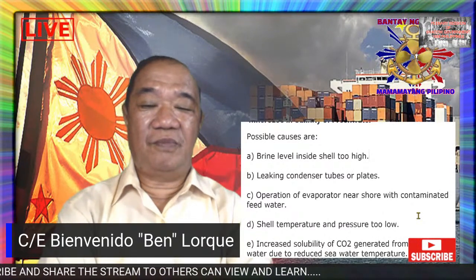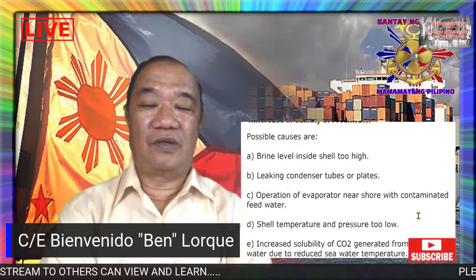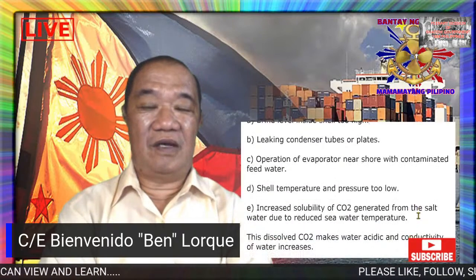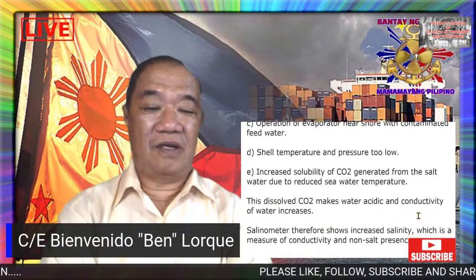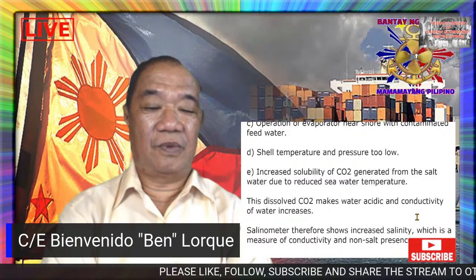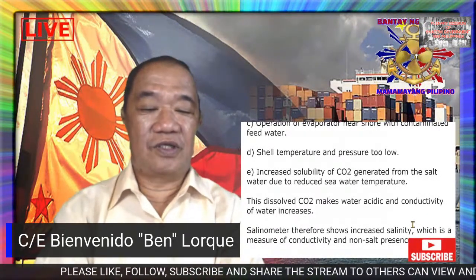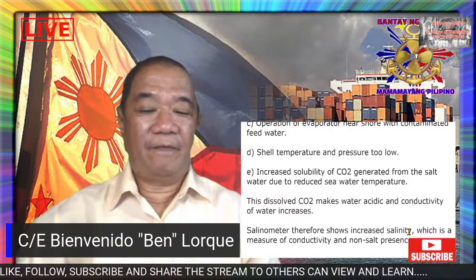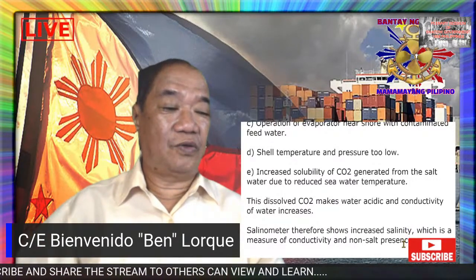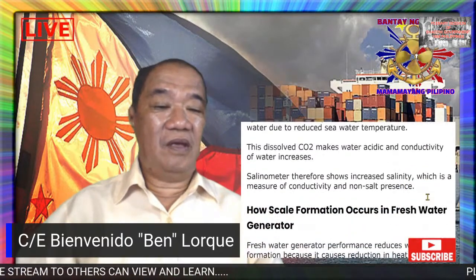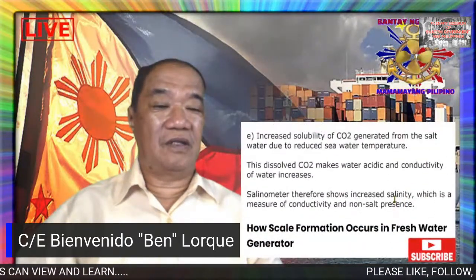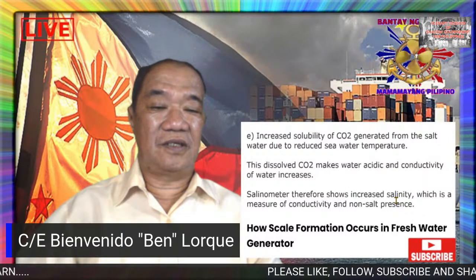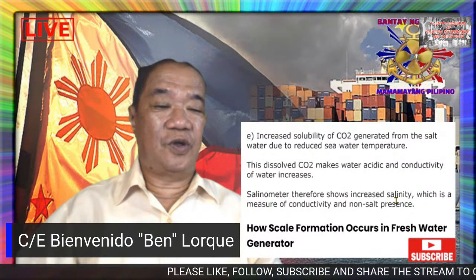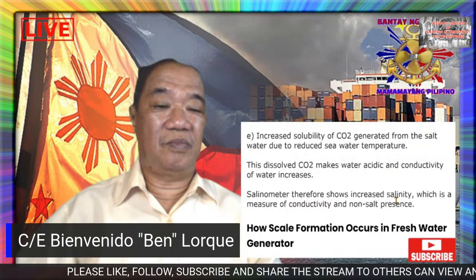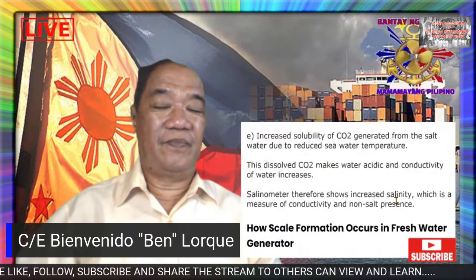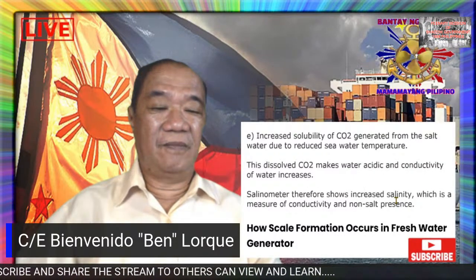So next, the shell temperature and pressure is too low. That will also cause an increase of the salinity reading, and increase the solubility of the CO2 generated from the salt water due to reduced seawater temperature. So this dissolved CO2 makes the water acidic and the conductivity of the water increases. The salinometer therefore shows increased salinity, which is a measure of conductivity and salt presence.